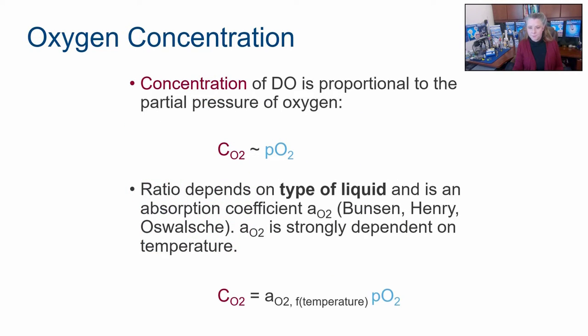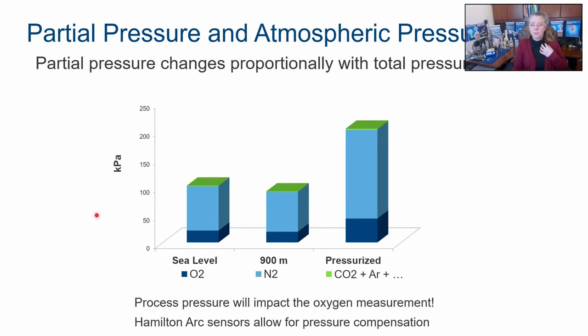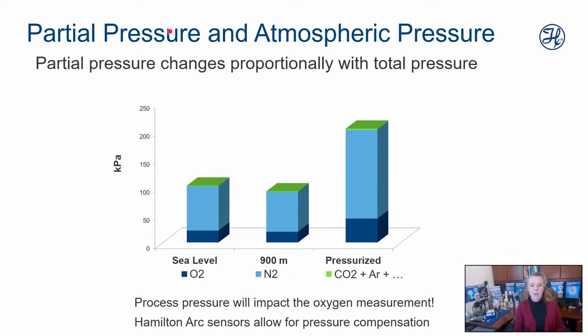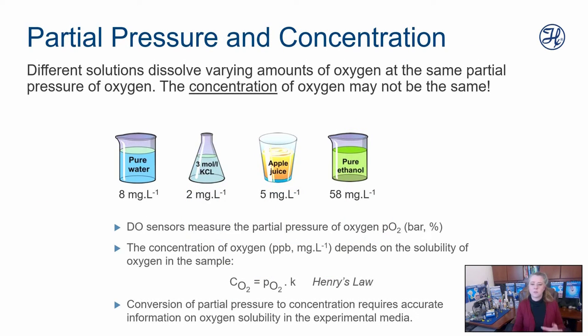So why do you care about any of that? Well, again, the concentration of oxygen is proportional to the partial pressure, and that depends on the type of liquid, what's in it. The solubility of oxygen in water very much depends on atmospheric pressure, as I talked about, but it also depends on what else is in solution. If we just look at pure water, we can get 8 milligrams per liter of dissolved oxygen. If we look at a saline solution like KCl, and we do add saline into our buffers, that is much less soluble. So salinity decreases solubility of oxygen.